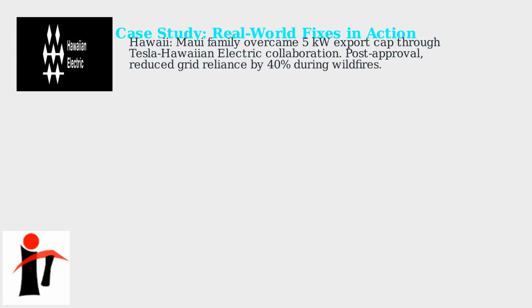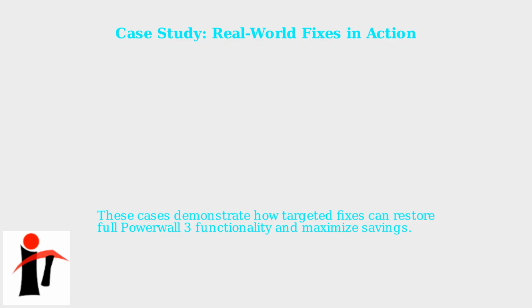Let's examine real-world examples of Powerwall 3 export fixes. In California, a San Diego homeowner experienced zero export because CTs were installed upside down. After Tesla's Q1 2025 firmware update and guided recalibration, the system began exporting at 7 kilowatts, resulting in $200 monthly savings. In Hawaii, a Maui family faced a 5 kilowatt export cap imposed by Hawaiian Electric. Through Tesla's collaboration with the utility, they obtained approval for limit overrides. This enabled them to export excess energy, reducing grid reliance by 40% during wildfires. These case studies highlight the effectiveness of proper CT alignment and utility limit overrides in resolving export issues.